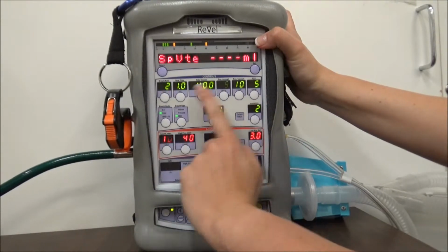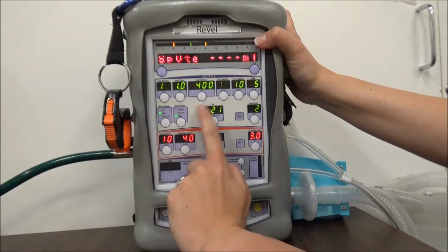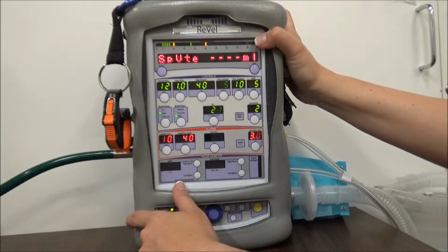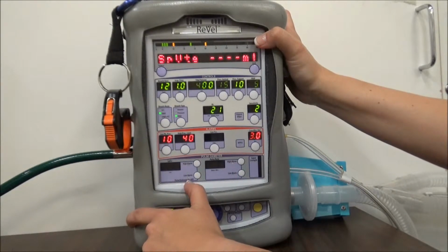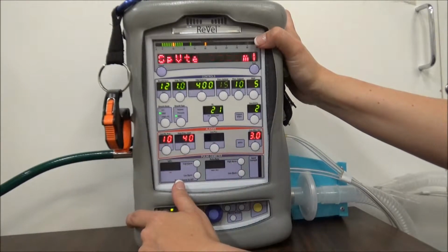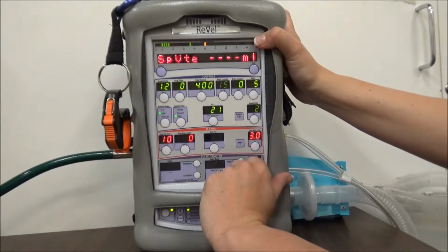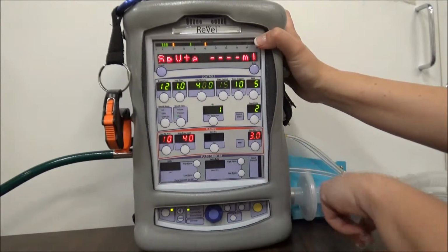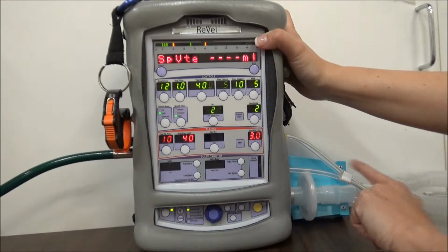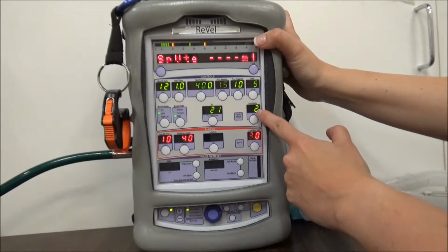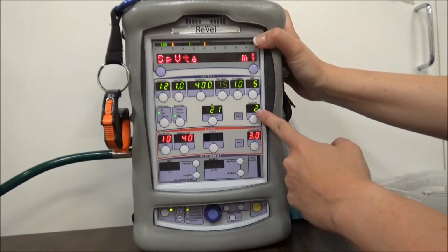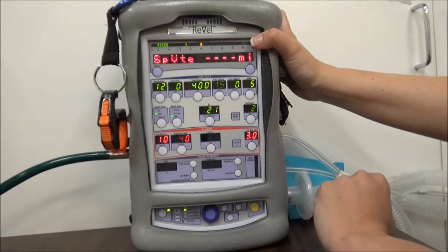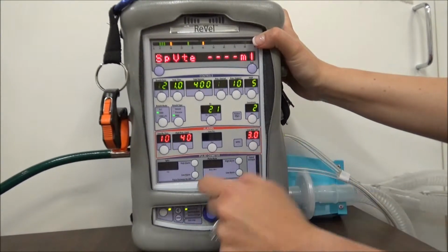So we've done this whole top row. We've picked SIMV, PRVC. We'll go down here and start our patients off on 100%, or if we're doing an interfacility transport, where they were at before. And then our patient sensitivity. 2 is a great place to be, and this is in liters per minute. So there's always 40 to 60 liters per minute flowing through this circuit. This means the patient has to trigger a change of 2 liters per minute for the ventilator to know that it wants a breath. You can change this up or down.